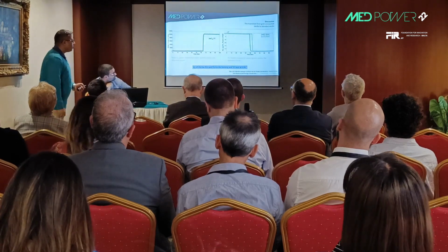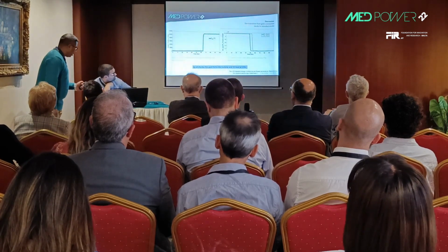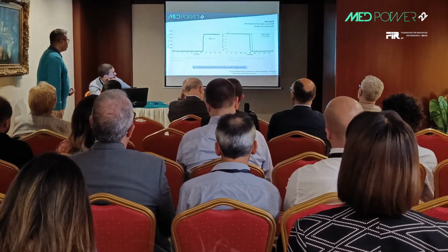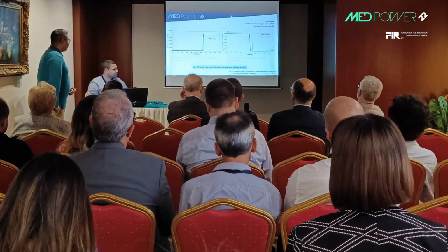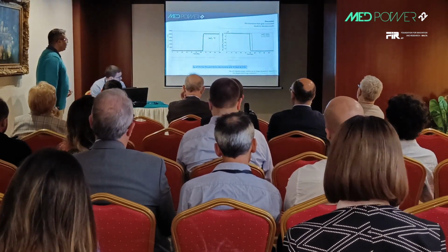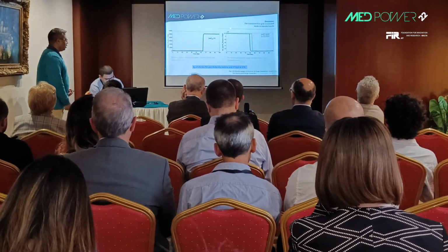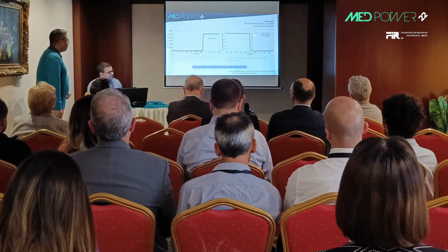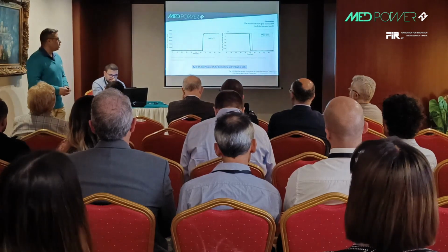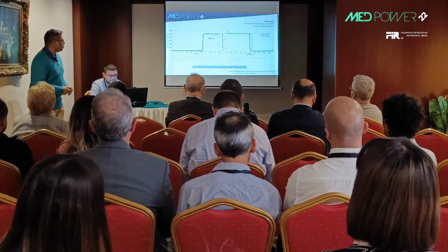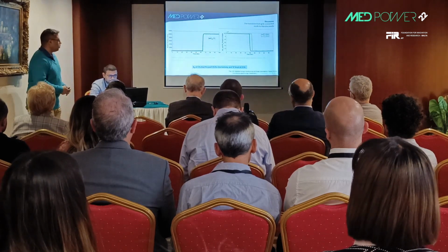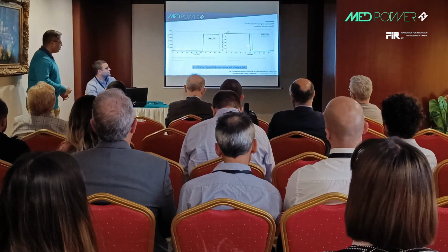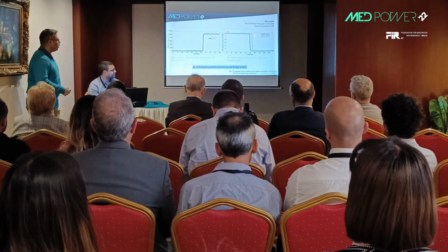These are some of the results we obtained using the real-time Typhoon HIL simulations. When we go from the grid connected mode to the islanded mode, the batteries and the PVs pick up power. They are part of different buses, so they still work in unison. This delay over here is only a recording delay. This is not the delay that is produced by the PVs per se. So the PVs enter from the MPPT mode to the VSG mode as soon as the grid goes into islanding.